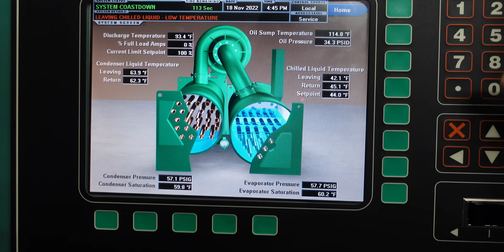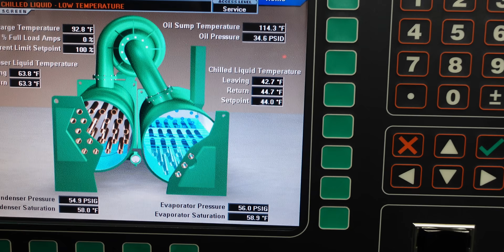Because we replaced the liquid level sensor, the old sensor was having problems, and I had to make some adjustments to the old metering valve actuator, which got done. Anyway, we replaced that actuator as well. I had to calibrate the actuator position so that the chiller had the correct position in order to control liquid level better. Regardless, those are just some minor adjustments we had to make. Not that big a deal. We just have a really low load. It's pulling down, it's cycling, everything's looking just fine.